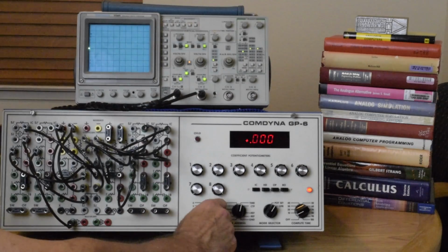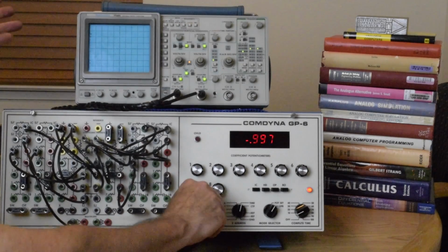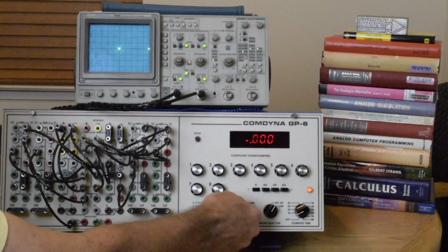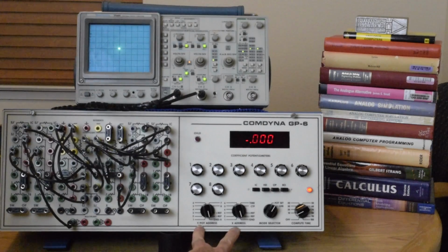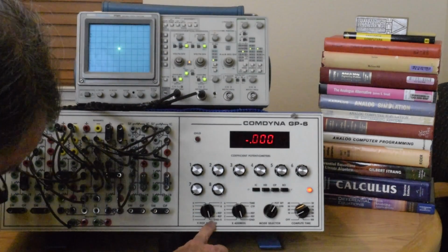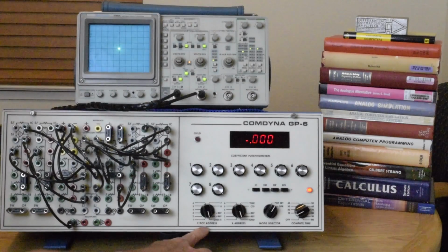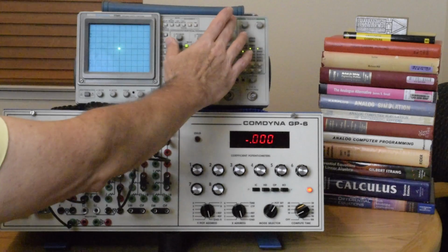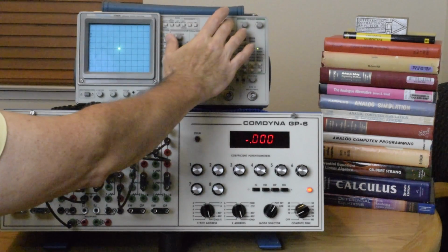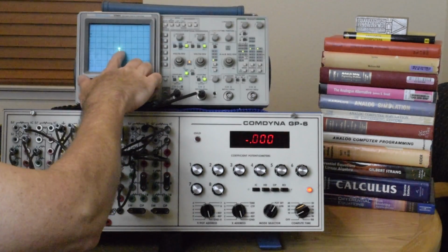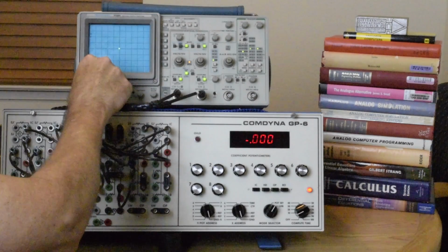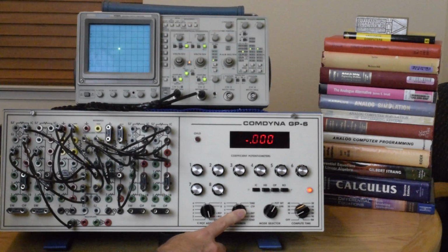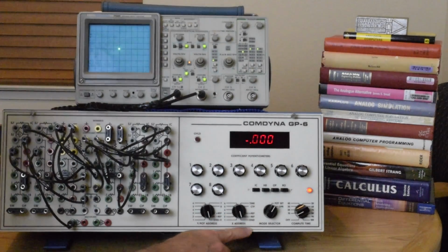In order to set up the oscilloscope, and I'll show you the XY mode on the oscilloscope later, the key is to set these two address pots, and you start with both of those on ground, and it's a little bit tricky. We want to adjust the horizontal position, which will determine where the dot is centered on the oscilloscope screen, so that calibrates the X zero position or X ground position.